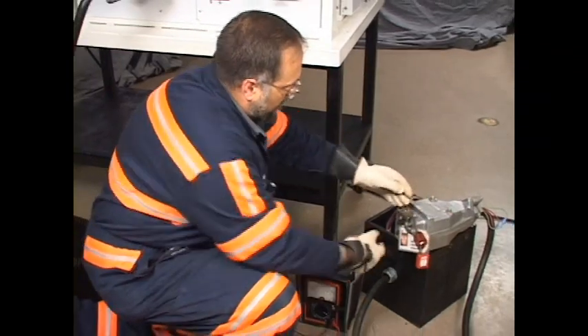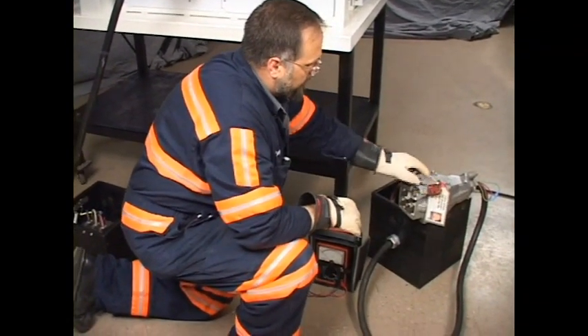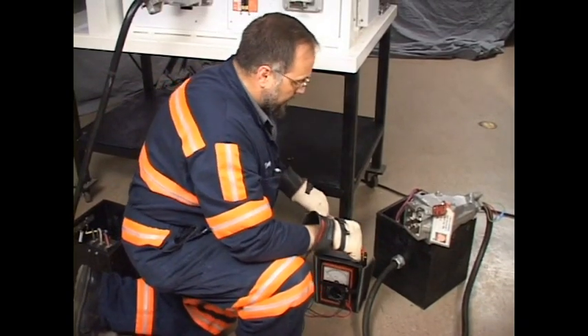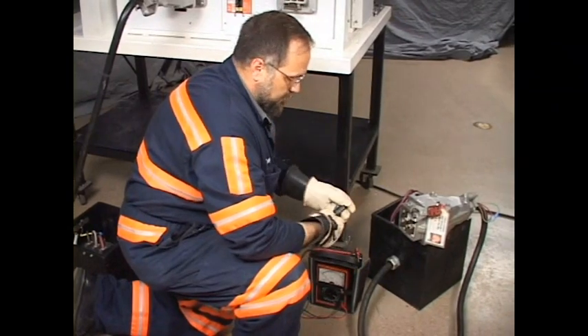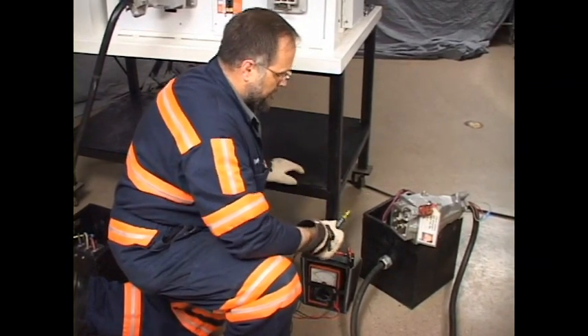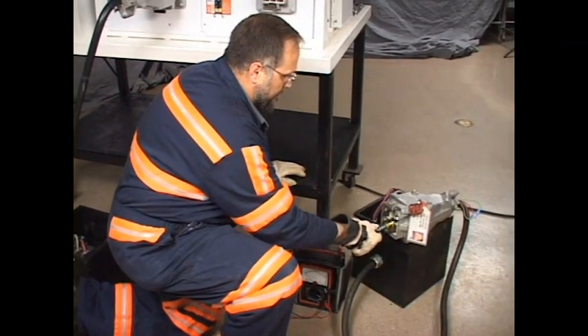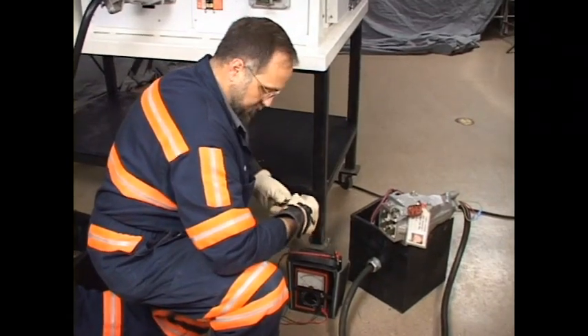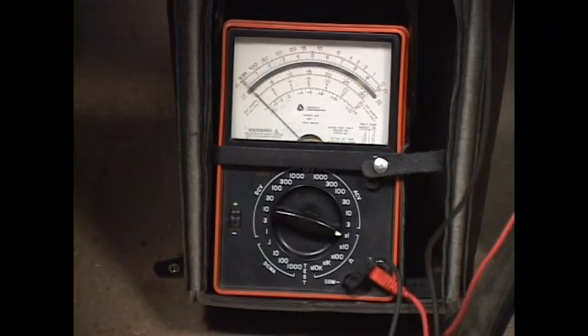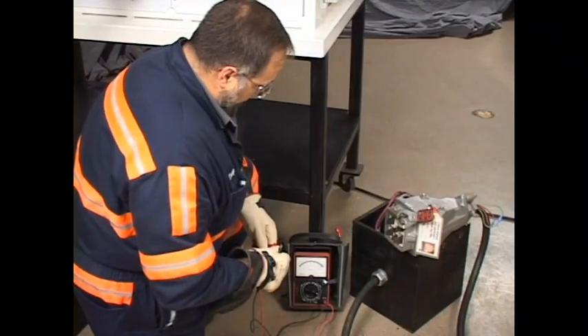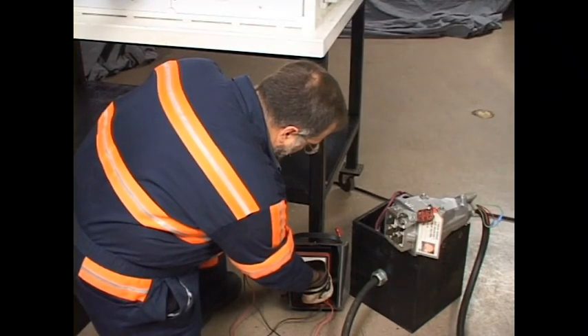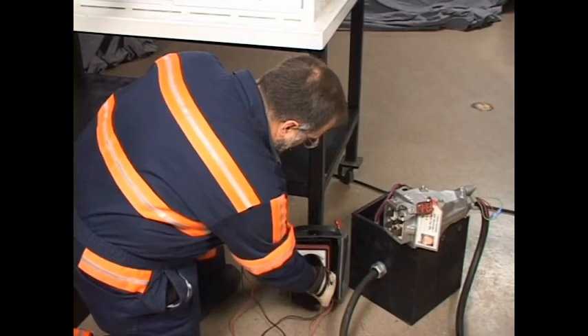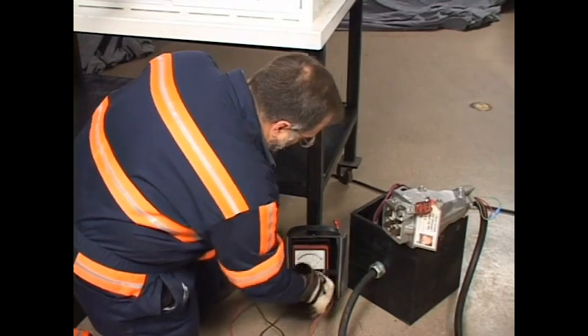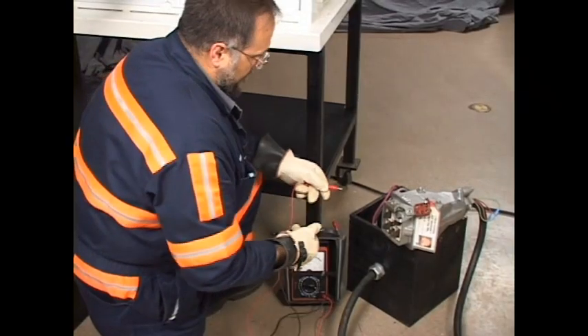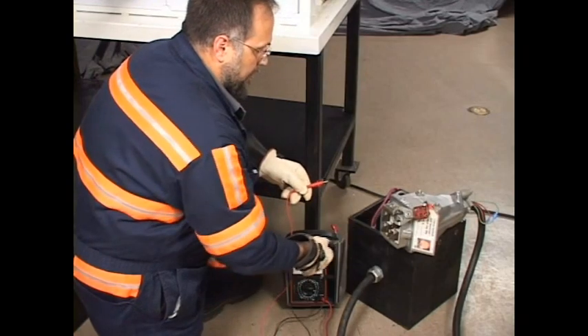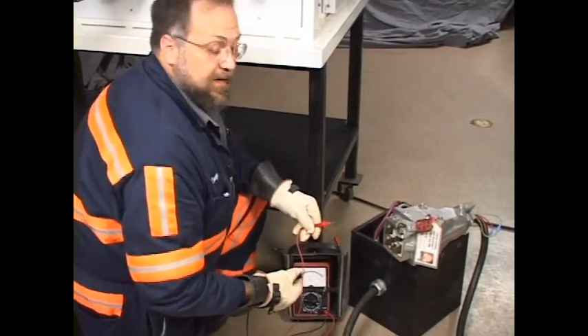Okay, although this circuit is disconnected from the power center at this point, the cable lies in close proximity to other cables that may indeed be energized on the section. So we won't assume that the power is off just because this one's disconnected. I'm going to make a voltage reading, make sure that these conductors are not energized, and they read clear. And then with my meter set for a continuity check, and we'll zero the meter. And with the meter zeroed, I'm going to check for ground continuity between the ground blade and the shell of the cathead. And for proper operation, we can't have any.